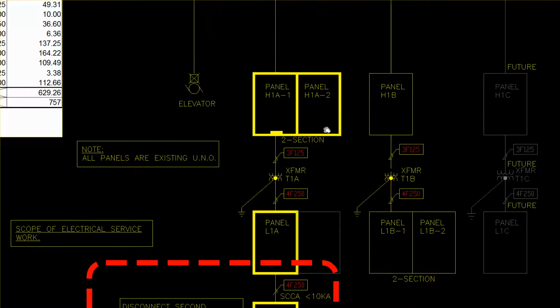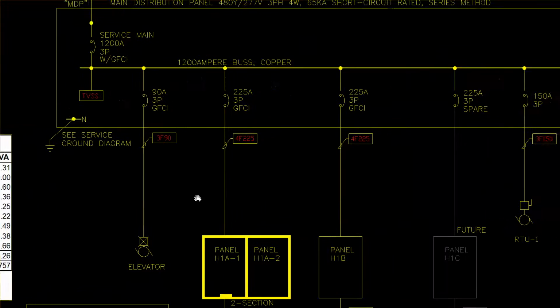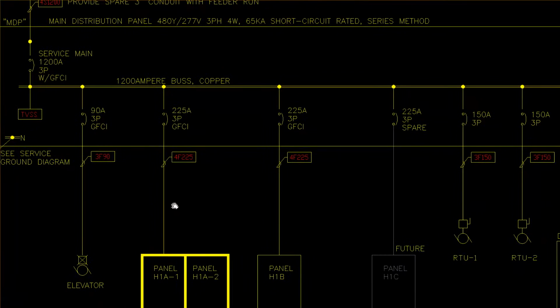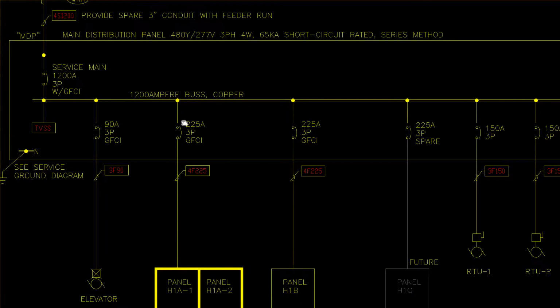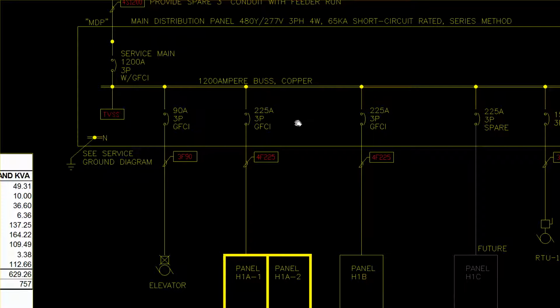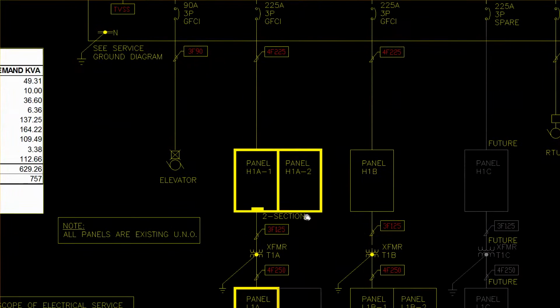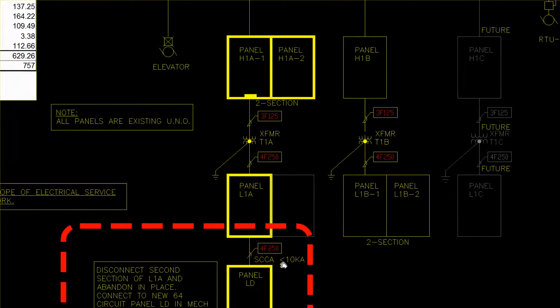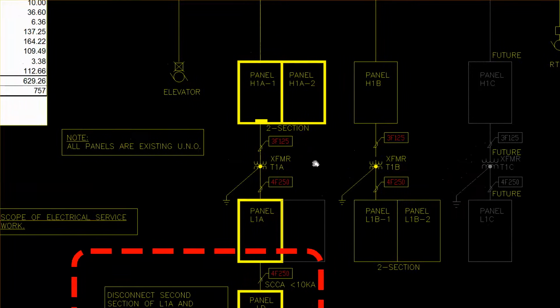In this particular case, I'm not sure if they got left on here because this was a remodel, but what you would typically see in this type of one line is that short circuit current study being set on there and scheduled, sometimes a fault current schedule, just like the feeder schedule. And then you'll see that SCCA equals, or equal to or less than or approximately, throughout. We would look for that, and that's something that's required before any panel board on here.